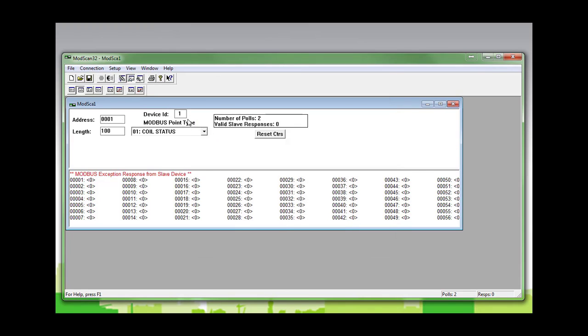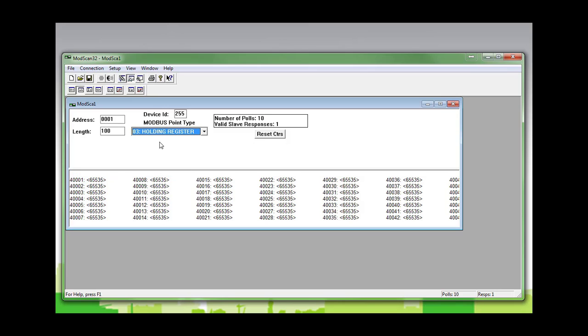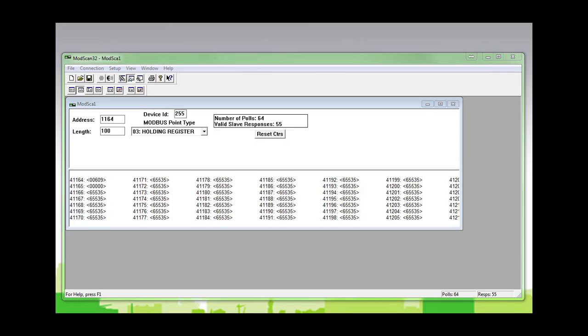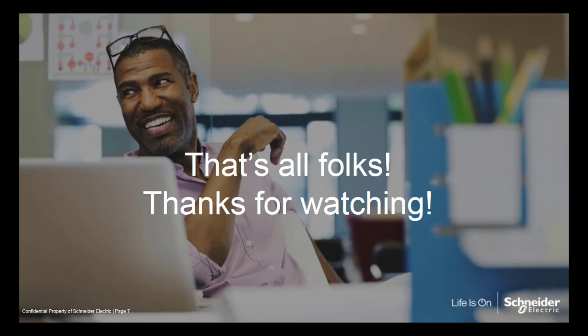So I connect to the meter, I type the device ID, which is 255, and I pick that it is a holding register. And do you remember the Modbus address? Yes, it's 41164. So we can see real-time values for the first two registers, and from 41165 there's no value. So that's all, folks.